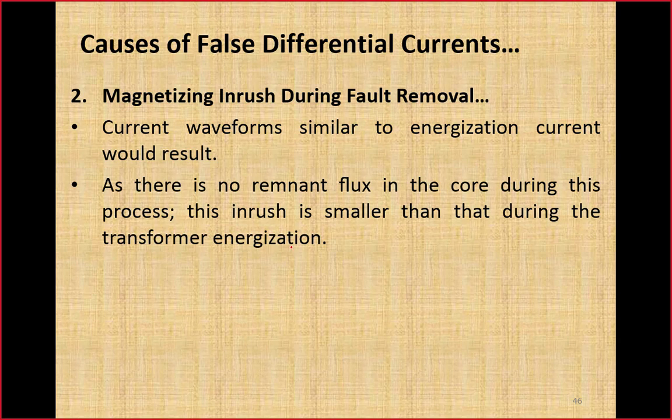As there is no remnant flux because the transformer is already energized, there is no residual flux. Due to this reason, the magnitude of inrush current will be a bit smaller as compared to the magnitude of inrush current during energization, but the nature of inrush current will be similar to the nature of inrush current during energization, meaning it has a deformed shape of current. Further, the current is full of harmonics, and the second harmonic will be dominant, but all other harmonics will be present in the current.